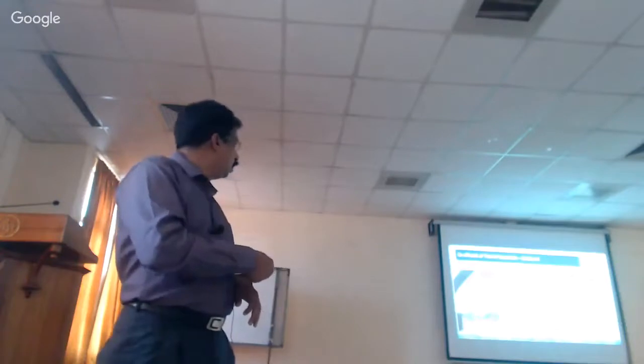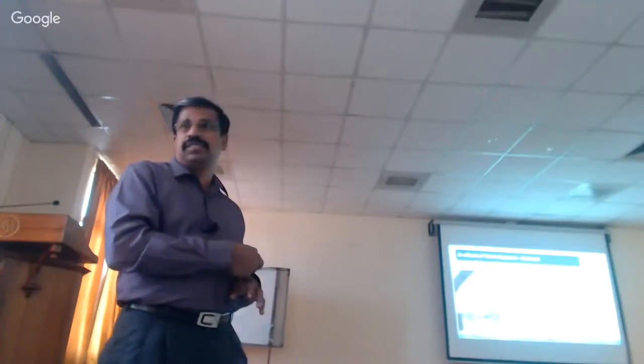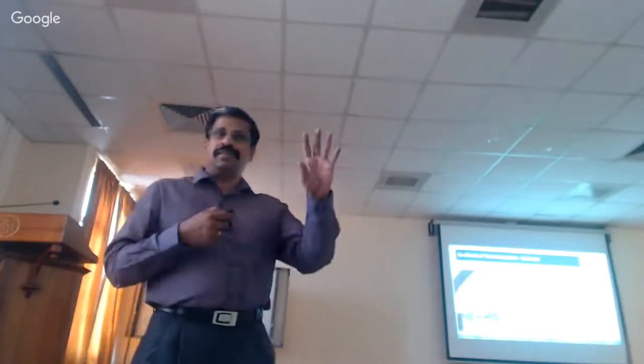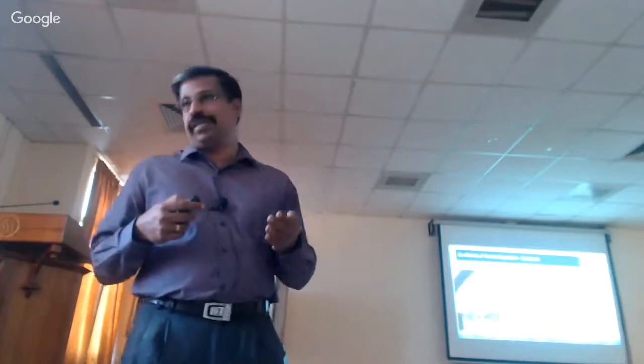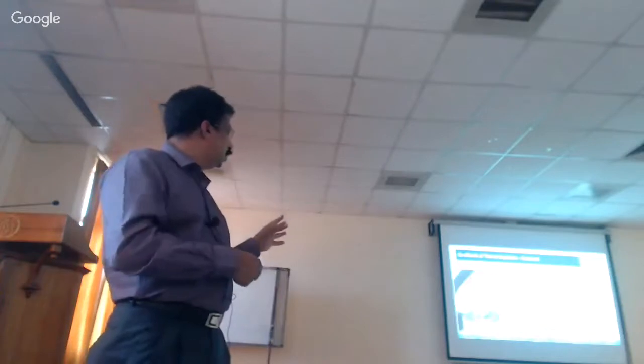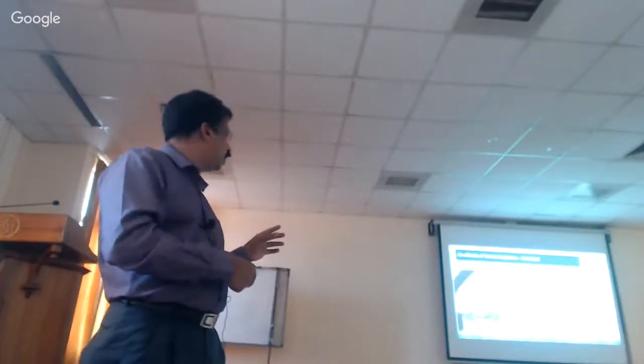Okay, this is how it is measured. There is a sample, a quartz stage and a quartz probe. Why quartz? That is the most dimensionally stable material. So it does not contribute much expansion, and only the sample contributes to the expansion measured.